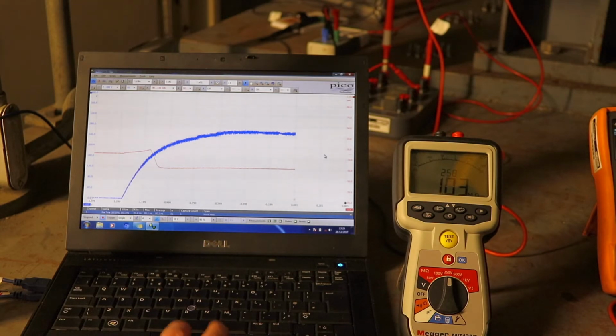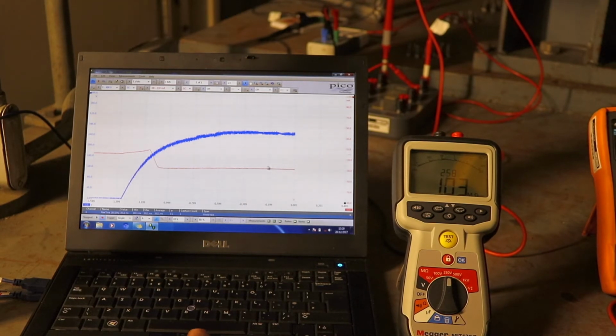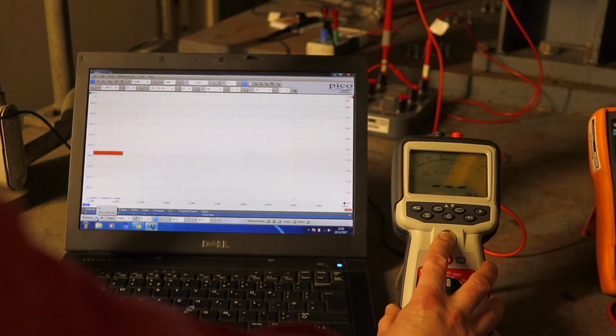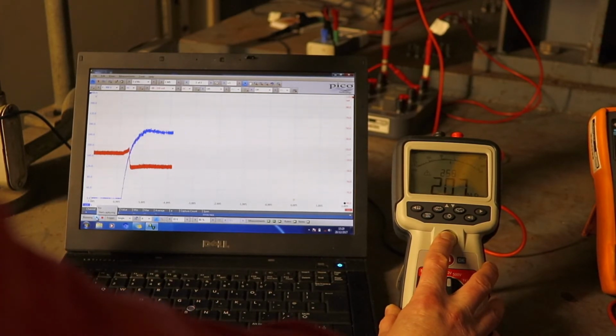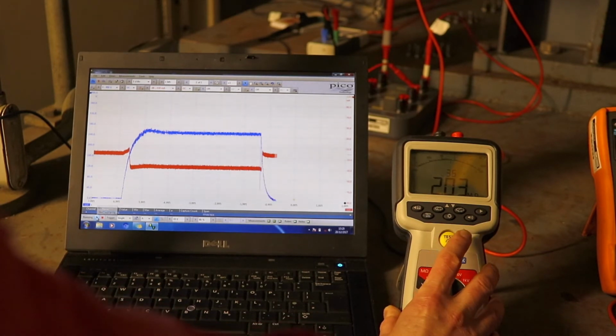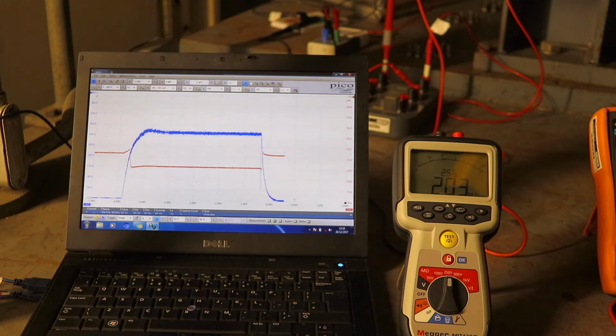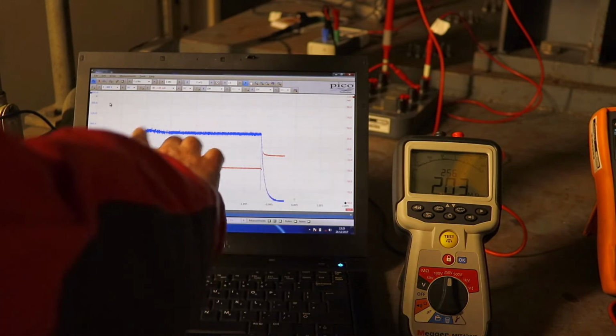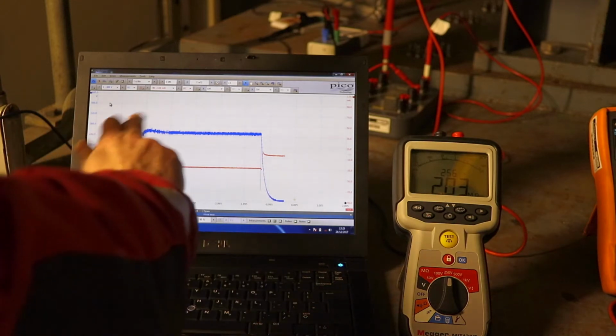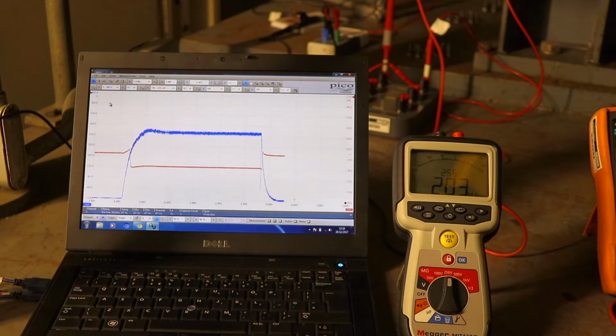So it's set up to a single shot, so I can show what happens. This is the Megger test. So that's the Megger test there, and you can see it's quite a steady rise, a little bit of overshoot on there, and before it dropped off, but you see the reading only gets to 2 megohms.